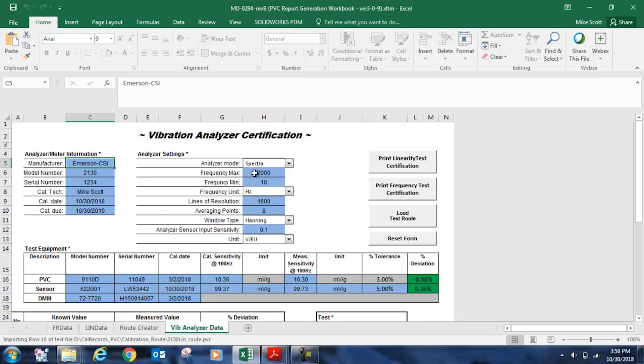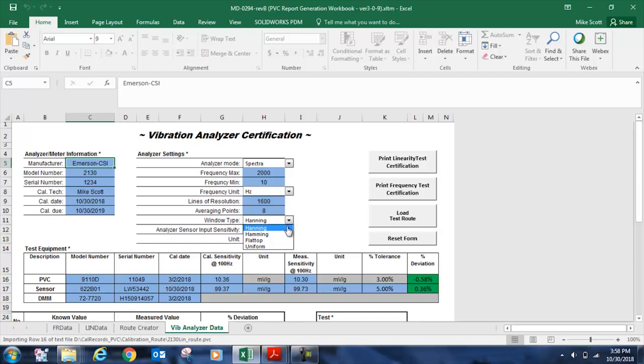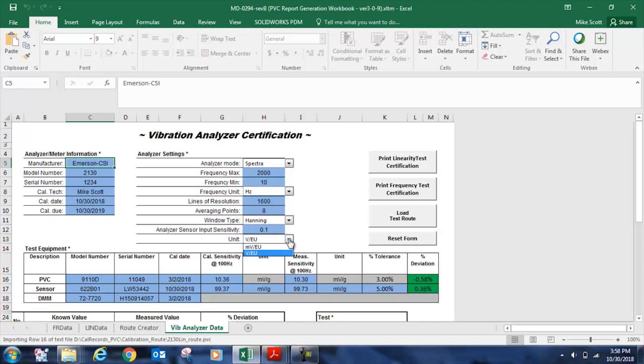Over here, I've noted my analyzer settings, which we showed in the previous scene. The analyzer was in spectra mode, but our other options here are overall and time waveform. Overall would be used for a basic vibration meter. We've noted our fmax and fmin in the frequency unit of hertz. Our other option is cycles per minute. Our lines of resolution and averages are noted here. Our window type is also selected as hanning, but we also have hamming, flat top, and uniform. And lastly, we've noted the sensor input sensitivity of 0.1 volts per engineering unit. We can also choose millivolts per engineering unit. And that was on the sensor input screen on the 2130.